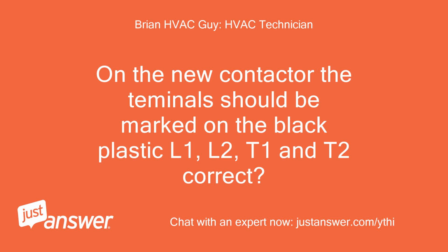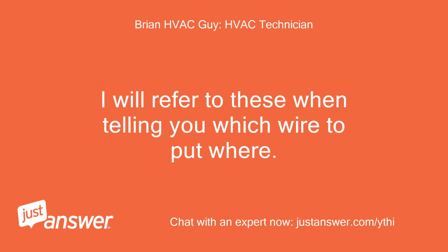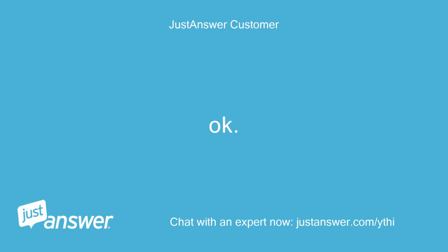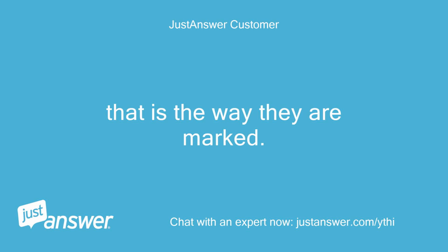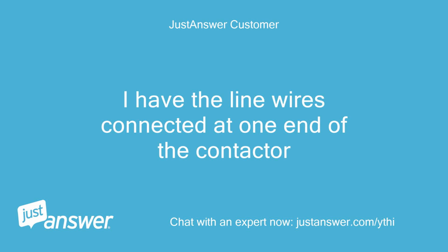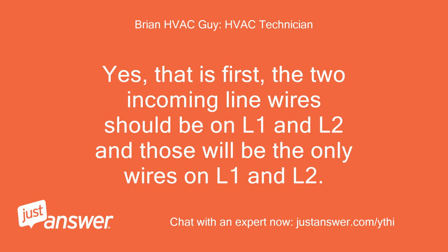On the new contactor, the terminals should be marked on the black plastic L1, L2, T1 and T2, correct? I will refer to these when telling you which wire to put where. Okay. That is the way they are marked. I have the line wires connected at one end of the contactor. Yes, that is first. The 2 incoming line wires should be on L1 and L2, and those will be the only wires on L1 and L2.